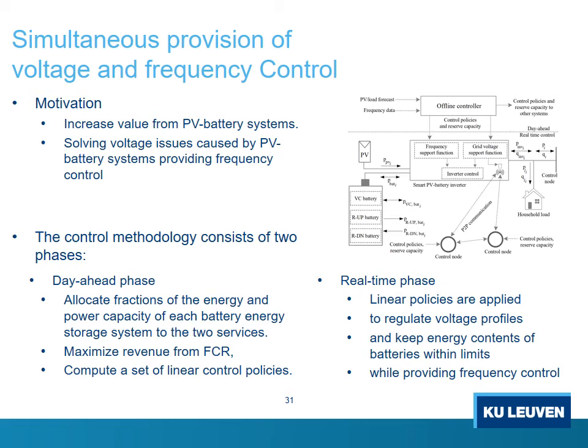So the message is, if you would like to use a battery energy storage system to provide a frequency containment reserve, you do need an energy management policy so that you are able to provide frequency containment reserve continuously, and you would have 100% availability of the service. Otherwise, your battery will be fully charged or fully discharged within a few hours. This is very important. In real time, the inverter consists of a grid voltage support function that applies the linear voltage control policies. Of course, the grid voltage support function has to communicate with other inverters because each policy is based on the power injection of the control nodes and the power injection of the other control nodes.